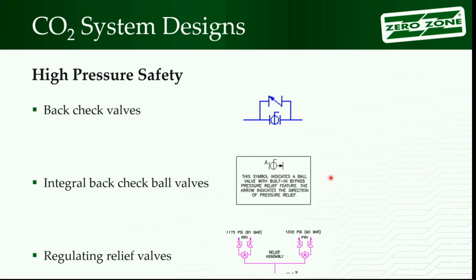Another item that can be used with that, and that by code is required in a lot of applications, is a regulating relief valve. With relief valves, once you get above a 6-inch diameter vessel, you're supposed to put a relief valve on it by code. That relief valve is designed so that in case of a fire, it's going to let the gas out of the tank so the tank doesn't explode, right? Fire, tanks exploding, people die. Refrigeration systems have been around, and all your systems have those relief valves.